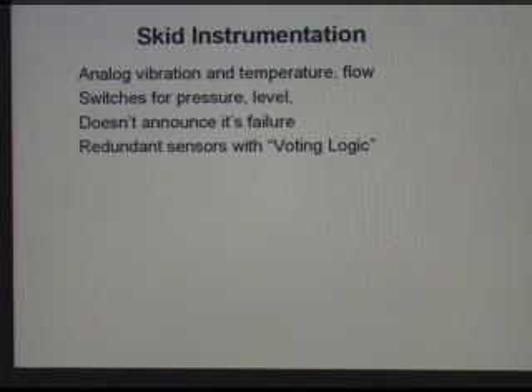Same thing with on-skid instrumentation. If it's an open circuit that has to close to cause an action, you don't know that it's actually going to do that until it physically does it, and that's when you need it. You have no way of verifying it'll do that before that point in time, unless you go into this huge maintenance cycle of always pulling every switch off, checking it, and then putting it back in again.